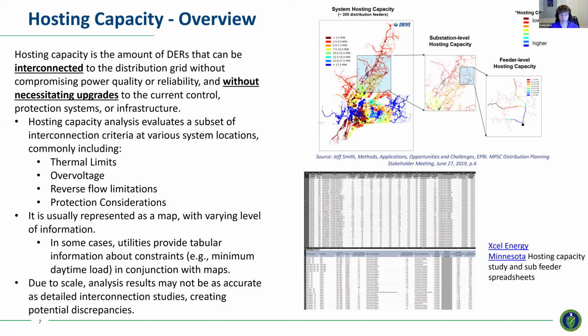Thermal limits are a big one. Over voltage comes into play if you have potential for voltage violations. Reverse power flow limits across equipment that cannot handle reverse power flow, either into the transmission system without the right protection upgrades, or regulator controllers or similar, and then some protection considerations as well. Generally, hosting capacity is shown in a map format, although it doesn't have to be.